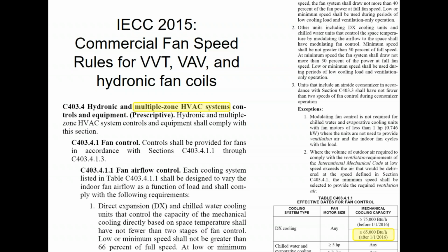You would still use the bypass damper if you were going to use a 2-speed fan operation. The fan would stage itself down based on how many stages of cooling we're running. So when we drop down from stage 2 of cooling to stage 1, the fan would go down to 2/3 of its fan speed, which just means your bypass damper would open less. That's all, because the fan would be providing less CFM.